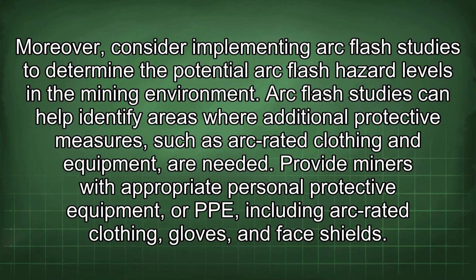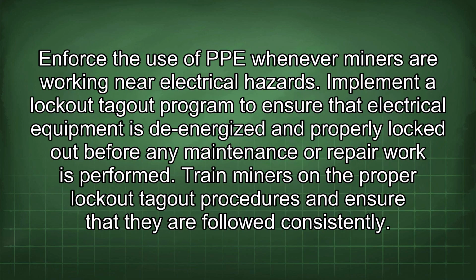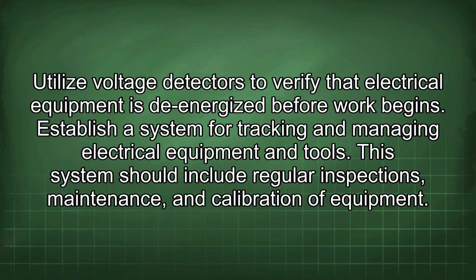Provide miners with appropriate personal protective equipment, or PPE, including arc-rated clothing, gloves, and face shields. Enforce the use of PPE whenever miners are working near electrical hazards. Implement a lockout-tagout program to ensure that electrical equipment is de-energized and properly locked out before any maintenance or repair work is performed. Train miners on the proper lockout-tagout procedures and ensure that they are followed consistently. Utilize voltage detectors to verify that electrical equipment is de-energized before work begins.